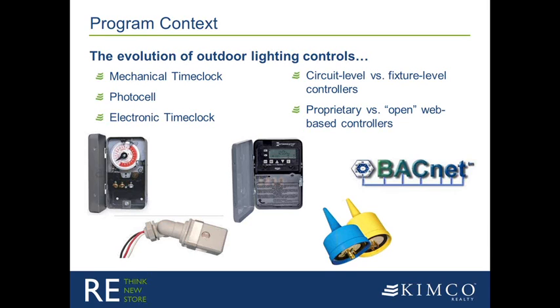You'll see the three components on the bottom left: the mechanical time clock, below that the photo cell, and above that an electronic time clock. These are probably your most common components used for outdoor lighting control. They're all very low cost and easy to install. The cons would be that they're all prone to user errors, both in terms of initial setup and ongoing operation. They're all prone to getting out of calibration over time, and none of them offer a remote connection for real-time monitoring or control of the lighting system.